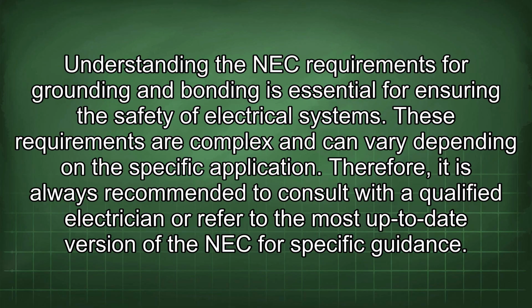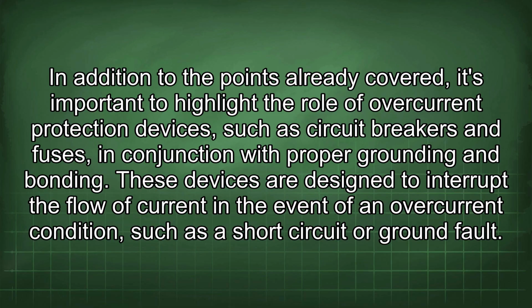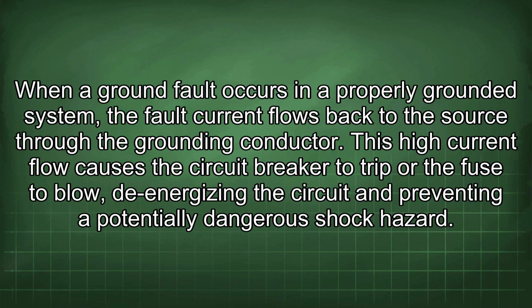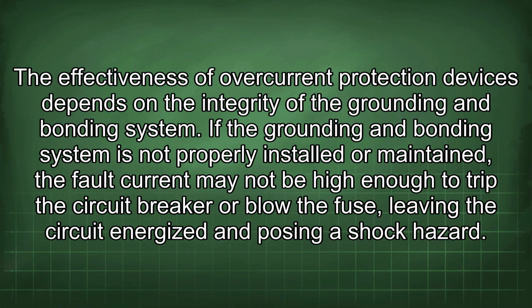NEC for specific guidance. In addition to the points already covered, it's important to highlight the role of overcurrent protection devices such as circuit breakers and fuses in conjunction with proper grounding and bonding. These devices are designed to interrupt the flow of current in the event of an overcurrent condition such as a short circuit or ground fault. When a ground fault occurs in a properly grounded system, the fault current flows back to the source through the grounding conductor. This high current flow causes the circuit breaker to trip or the fuse to blow, de-energizing the circuit and preventing a potentially dangerous shock hazard. The effectiveness of overcurrent protection devices depends on the integrity of the grounding and bonding system.